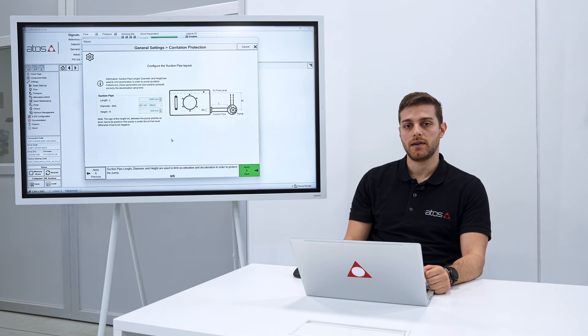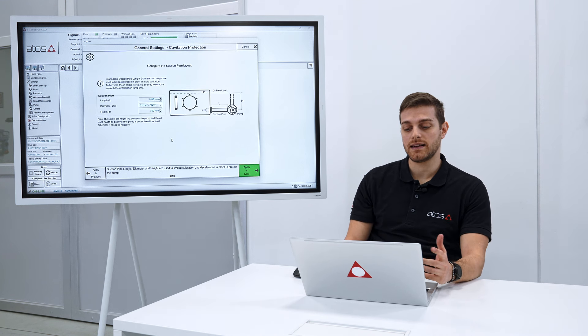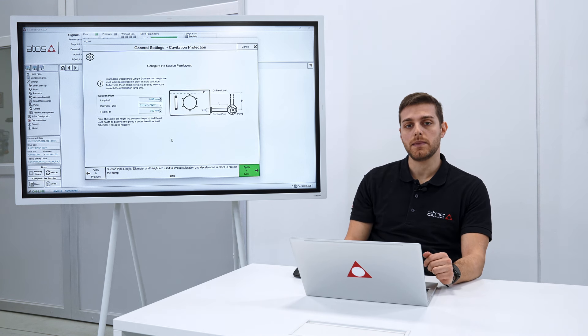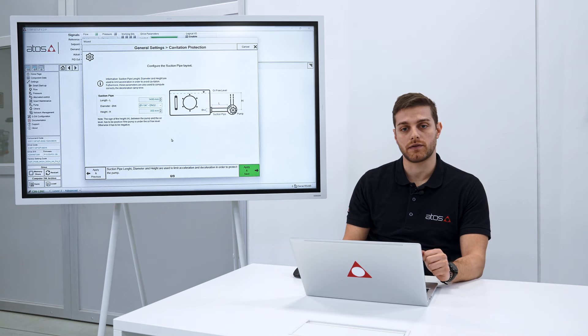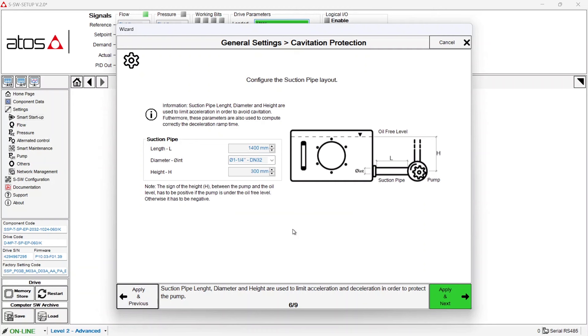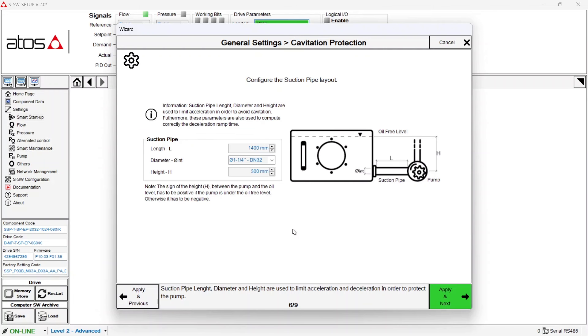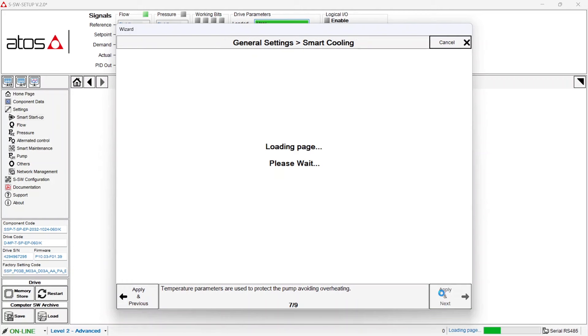Now this step is instead needed in order to limit the maximum acceleration of the servo pump in order to avoid cavitation of the pump. To do it you need to insert the parameters of your suction pipe layout. Once you have done it you can go on.